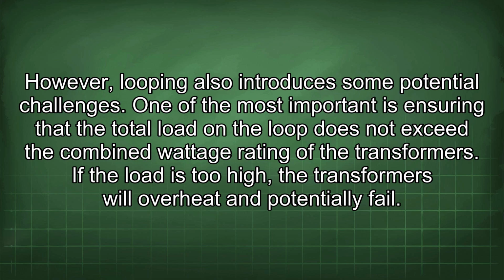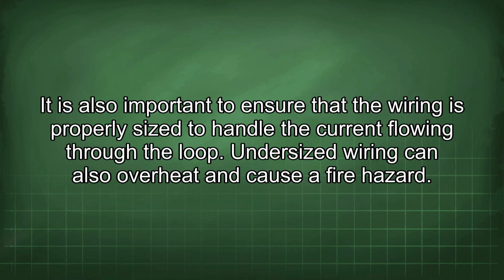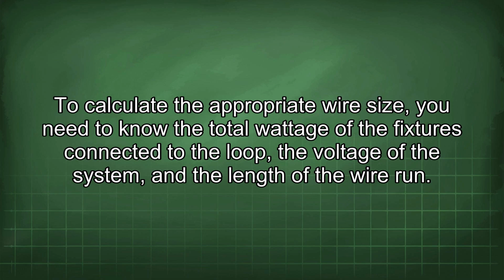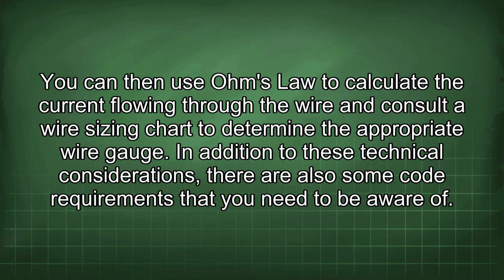However, looping also introduces some potential challenges. One of the most important is ensuring that the total load in a loop does not exceed the combined wattage rating of the transformers. If the load is too high, the transformers will overheat and potentially fail. It is also important to ensure that the wiring is properly sized to handle the current flowing through the loop. Undersized wiring can also overheat and cause a fire hazard. To calculate the appropriate wire size, you need to know the total wattage of the fixtures connected to the loop, the voltage of the system, and the length of the wire run. You can then use Ohm's law to calculate the current flowing through the wire and consult a wire sizing chart to determine the appropriate wire gauge.